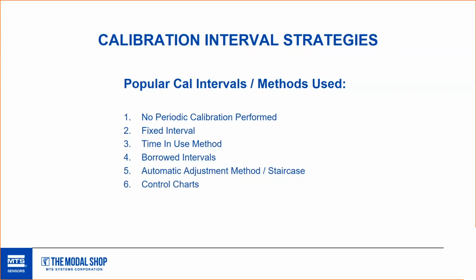And finally, control charts. They can be used on an as-needed basis to track behavior on a more frequent basis: weekly, daily, or even before and after a measurement. It's very time-consuming, but identifies when accuracy fails based on any number of factors, including the sensor, the environment, or even the operator. A daily calibration is often performed as verification for a working reference sensor when we use back-to-back calibrations in our lab. And a control chart of that working reference or the verification sensor is a method to tightly control such an important piece of the traceability chain.